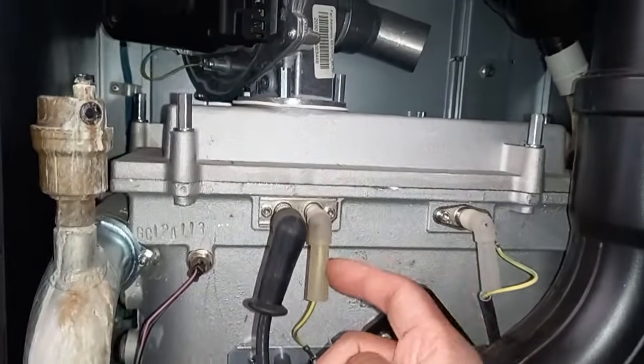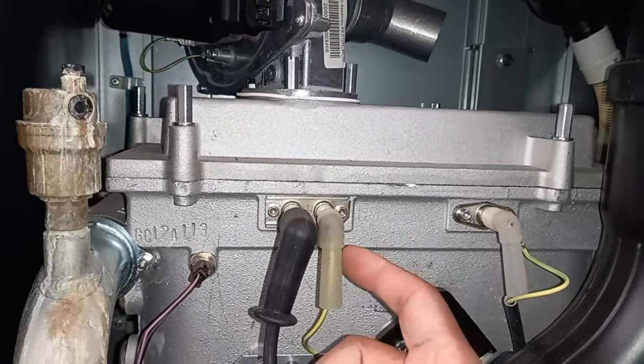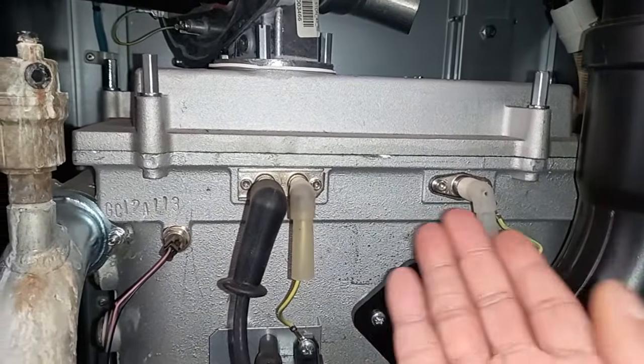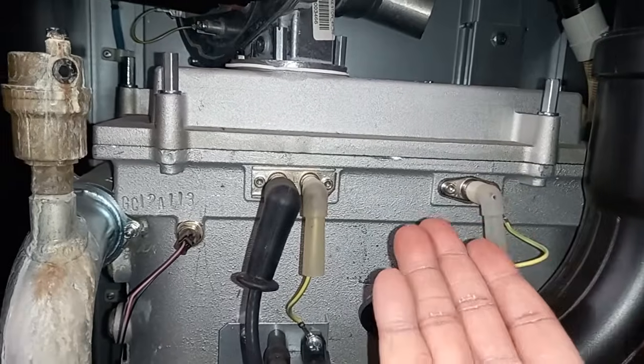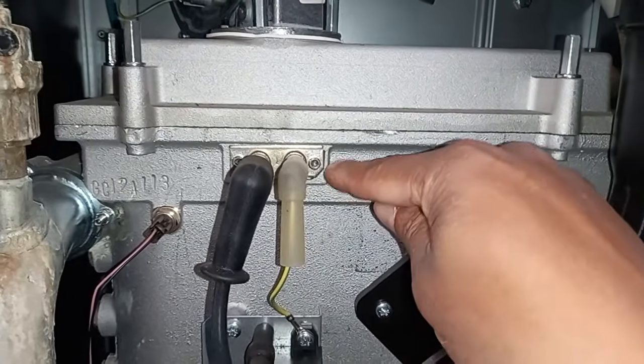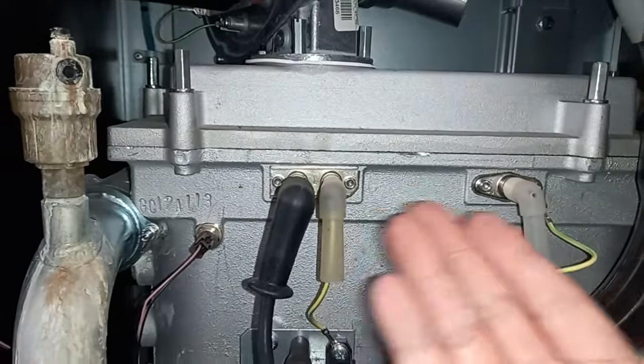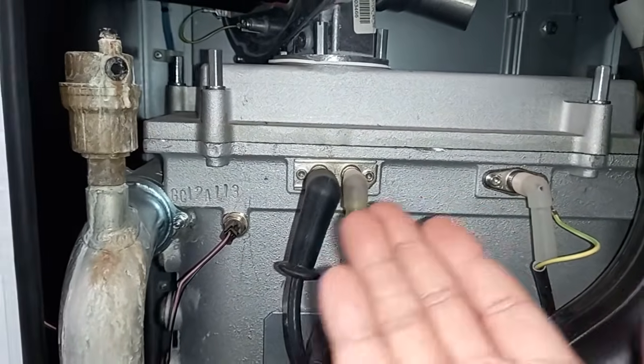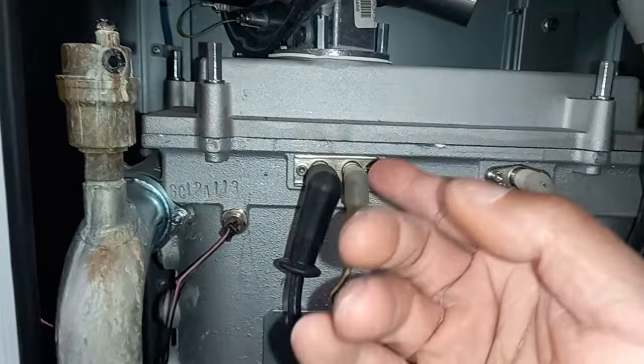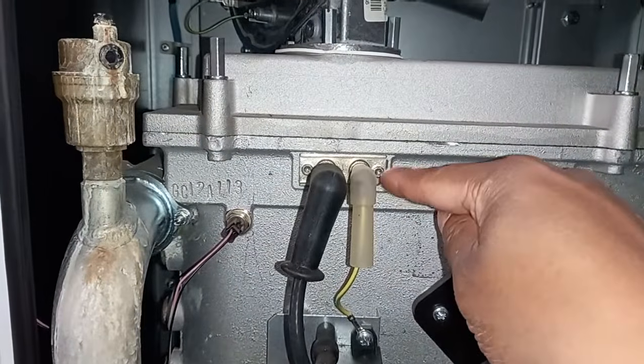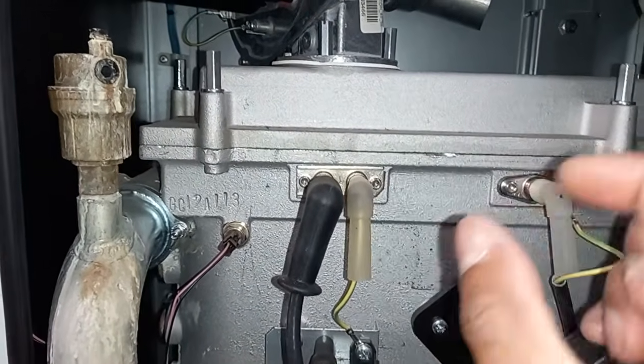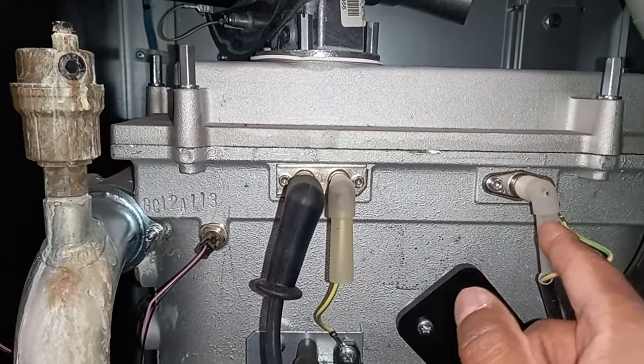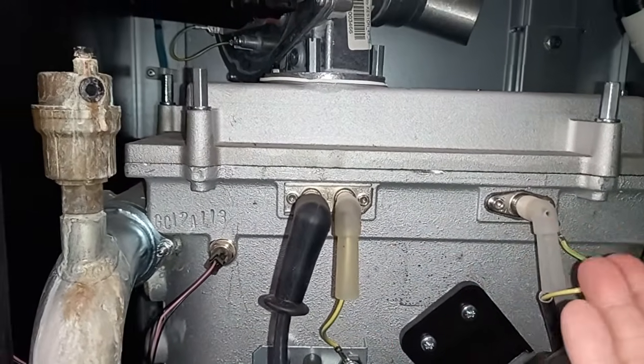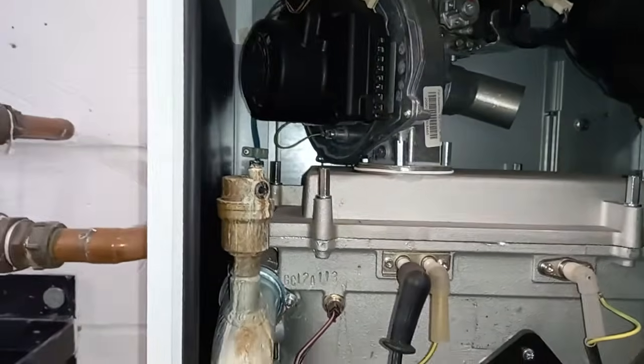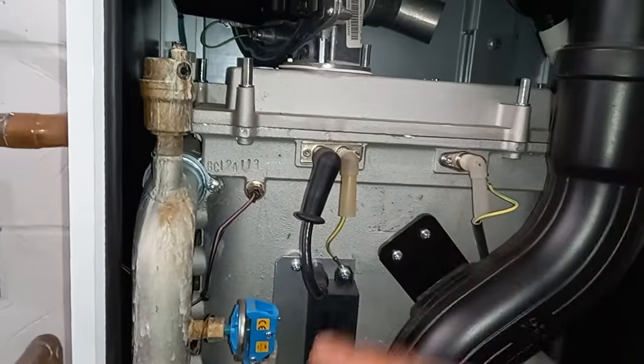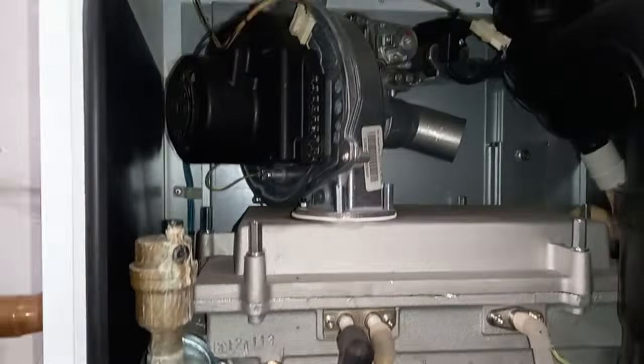Okay, and then these probes here, ideally you want to change them on a service, but if you haven't got the service kit, you can't change them. But in certain scenarios, if you've got some of these gaskets here in good condition, you can clean the probes up, especially if you come on a call out and the boiler's not lighting. There's nothing wrong with taking these out, so long as the gasket is okay underneath, and you clean up the probes, check their distance and the detection, so spark and detection, and make sure they're in good condition, and the boiler is likely to light, because these are the most likely things to go on a boiler when they're not changed.